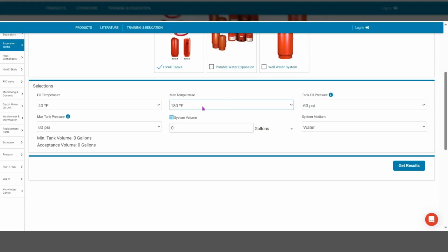There's not much load, so the temperature will start to creep up on the return side, and you will start to approach this maximum temperature. So it will slightly oversize the tank, but at the same time, it gives you a little bit of safety factor, particularly if somebody operates it differently than you were expecting them to. So we'll leave it at 180.